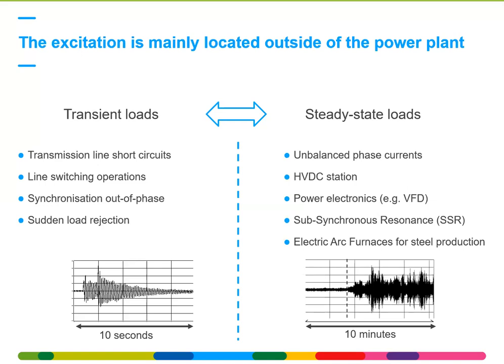In steady state loads, you have as examples unbalanced phase currents. So the natural imbalance of the three phases on the grid that you have the entire time. You could have HVDC stations nearby the power plant, power electronics, subsynchronous resonance will be detailed further on. Or large consumers like electric arc furnaces for steel production nearby the power plant. These are all examples where you have excitations during a much longer time span. So an example is given below in the figure where you have, for instance, 10 minutes. It could go up to 1 hour, several hours. So depending on the phenomenon.